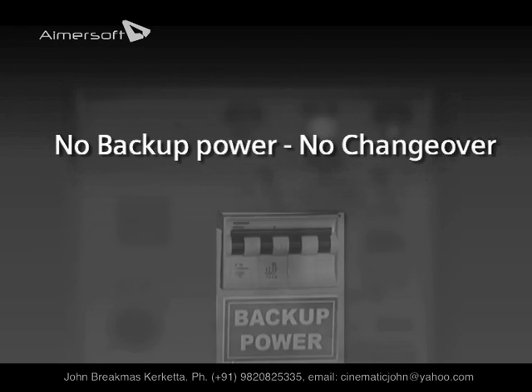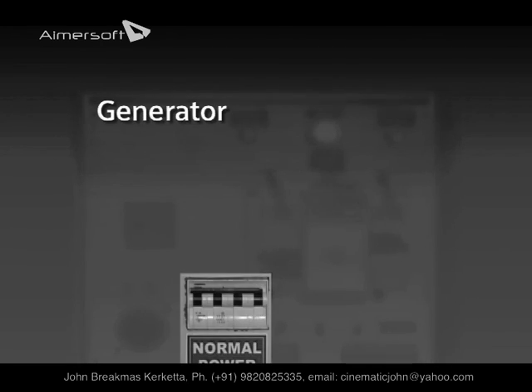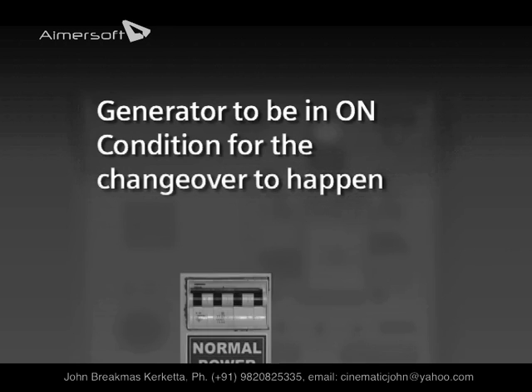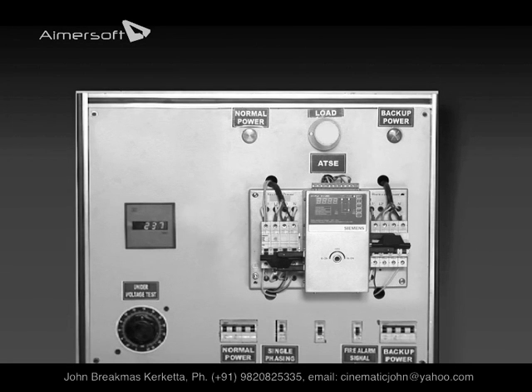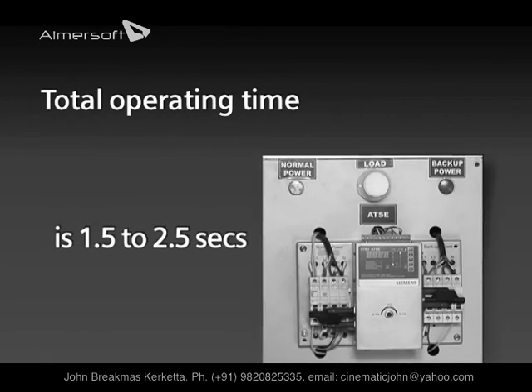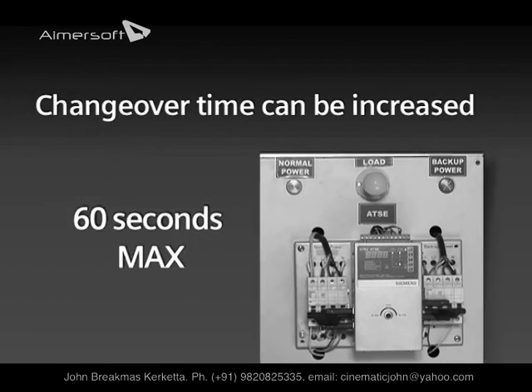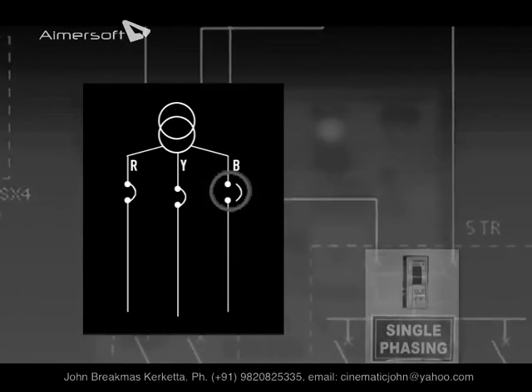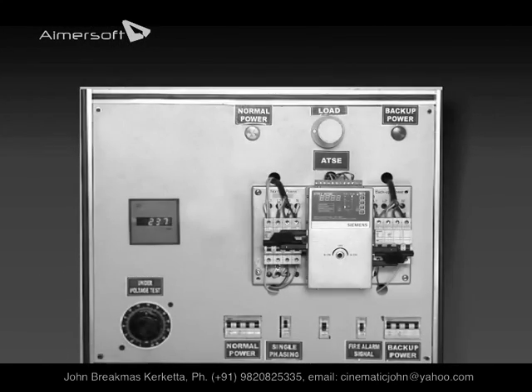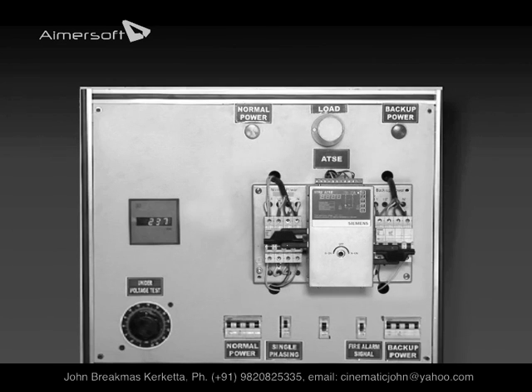In the event of a power failure, the ATSE mechanism gets the signal and changes over to the backup power source. Please note that the changeover will happen only when backup power is available — if the generator is not started, the changeover will not happen. Once the main power resumes, the ATSE controller gives the signal and the MCB on the normal power side is turned on. The changeover time is 1.5 to 2.5 seconds, but can be increased up to 60 seconds. In case of failure of any phase of the normal supply, the ATSC automatically switches to the backup source, and returns to the original position once normal supply is restored.